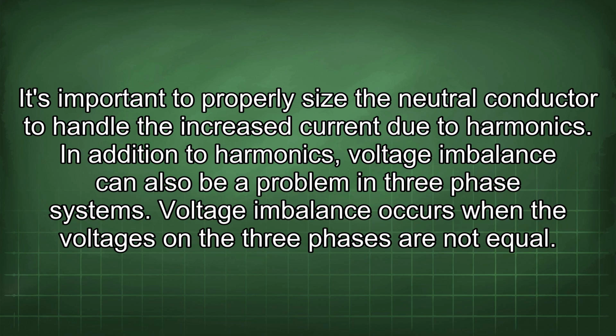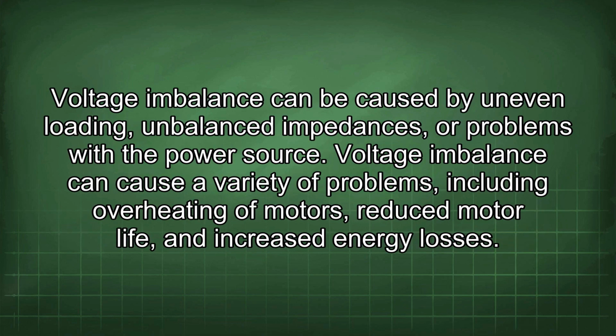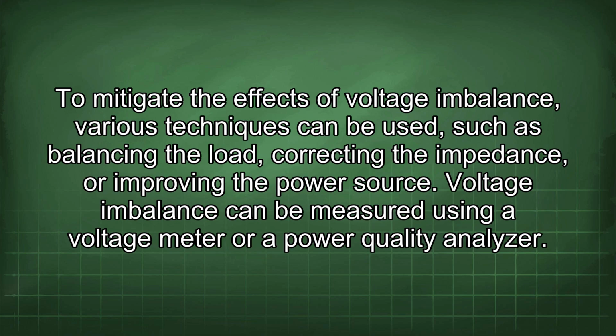In addition to harmonics, voltage imbalance can also be a problem in three-phase systems. Voltage imbalance occurs when the voltages in the three phases are not equal. Voltage imbalance can be caused by uneven loading, unbalanced impedances, or problems with the power source. Voltage imbalance can cause a variety of problems, including overheating of motors, reduced motor life, and increased energy losses. To mitigate the effects of voltage imbalance, various techniques can be used, such as balancing the load, correcting the impedance, or improving the power source.